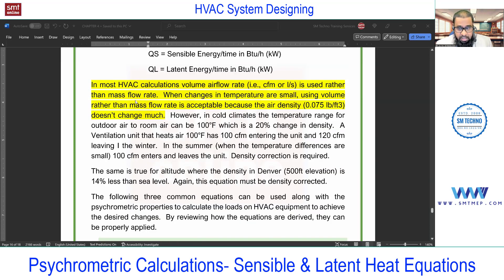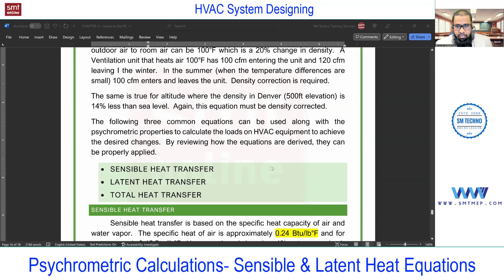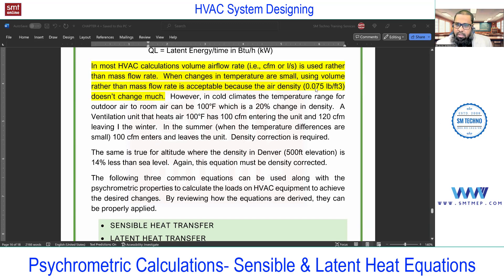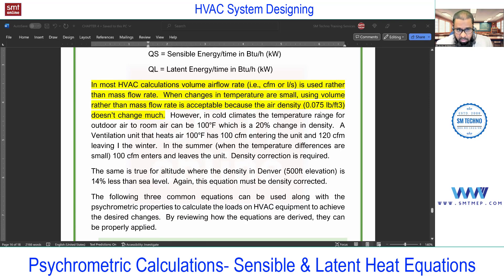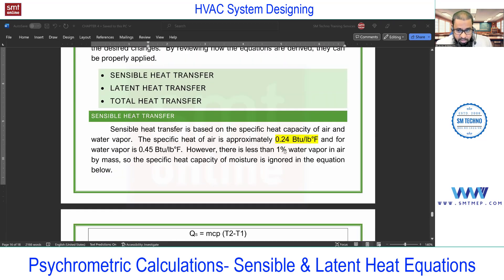Before the sensible heat formula, you must know the air density value we'll use. We are considering air density as 0.075 pounds per cubic feet — this is a standard value, just like water density or other fluid densities. This is in the English system; in the metric system this number will change. So 0.075 lb/ft³ means if you take one cubic foot of air, the weight is going to be 0.075 pounds. We'll use this value in the next equation.